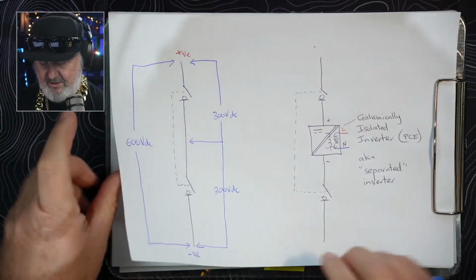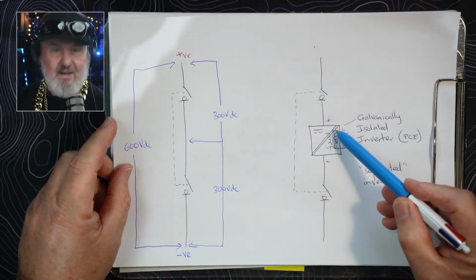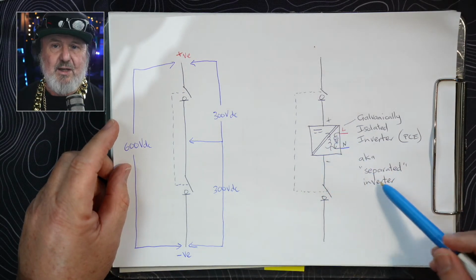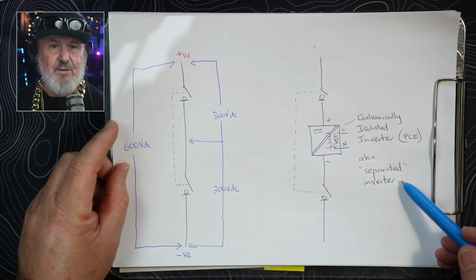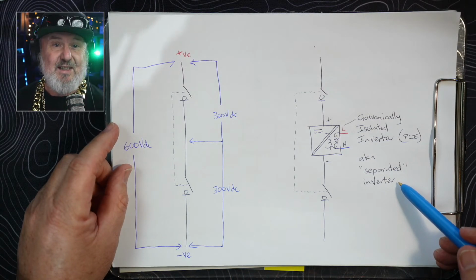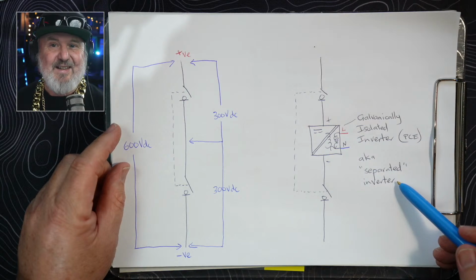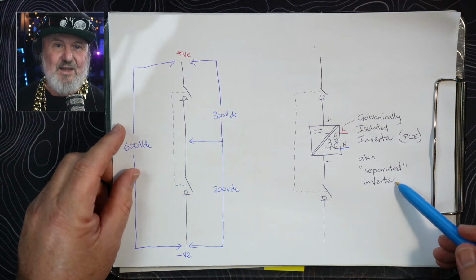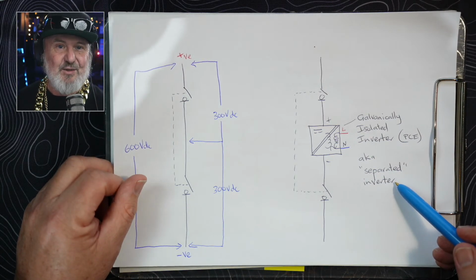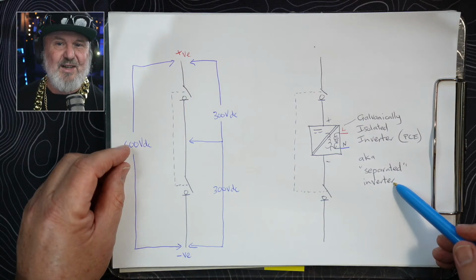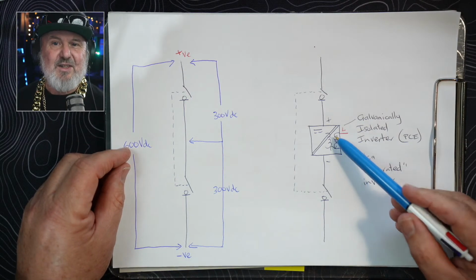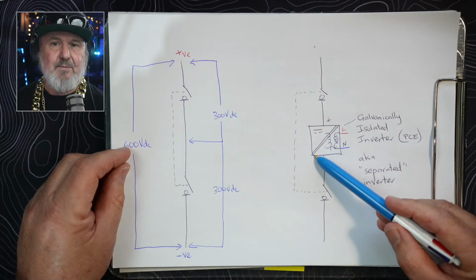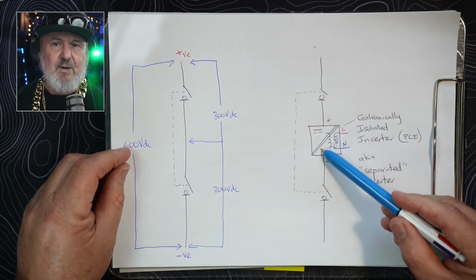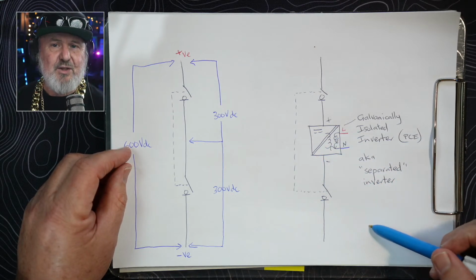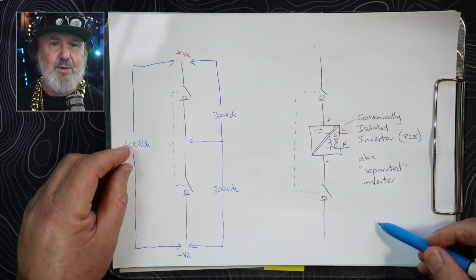And by the way, the symbol for galvanically isolated, which more technically is known as separated inverter, even more technically, simple separation. So simple separation is just some varnish on some windings on a transformer, and you're just relying on inductance to pass the energy. Is this double line. So this double diagonal line here represents simple separation within the product, within the PCE.